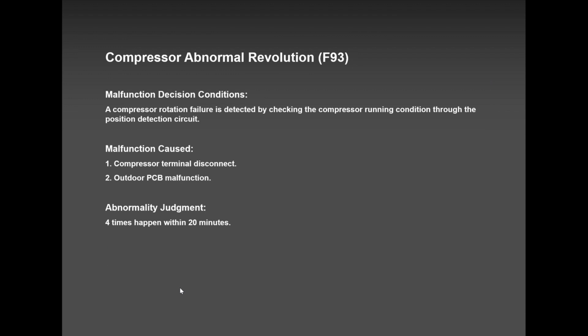F93 is to do with compressor problem, and the compressor problems can be caused by pipe kinks. In this section here, there is no way it talks about pipe kinks, but I'm telling you based on my field experience. A few guys with this error code, we concluded that there were kinks in the pipe.